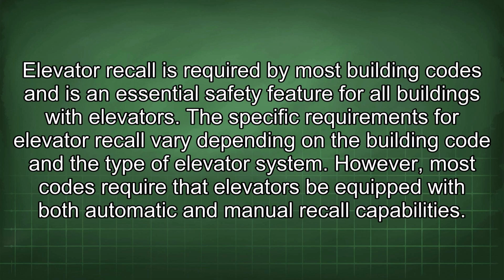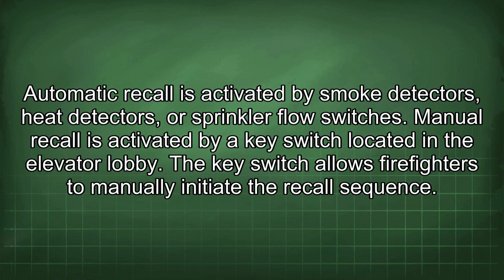Elevator recall is required by most building codes and is an essential safety feature for all buildings with elevators. The specific requirements for elevator recall vary depending on the building code and the type of elevator system. However, most codes require that elevators be equipped with both automatic and manual recall capabilities. Automatic recall is activated by smoke detectors, heat detectors, or sprinkler flow switches. Manual recall is activated by a key switch located in the elevator lobby. The key switch allows firefighters to manually initiate the recall sequence.